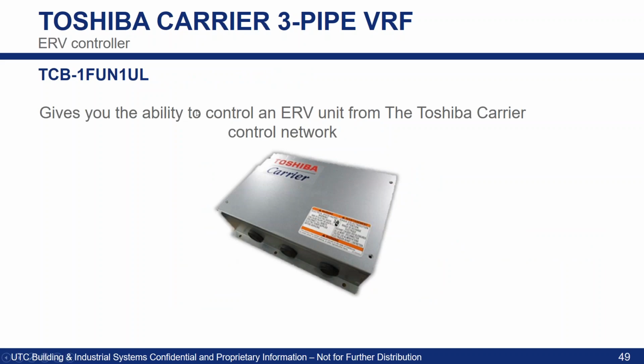So an ERV controller gives you the ability to control an ERV unit from a Toshiba-Carrier control network. So really, guys, this is the controller that we can integrate into our VRF control system that could turn on an ERV. It could also enable a DOAS unit. And this could all be run through our control system so it can be scheduled. So just a nice add-on there if you don't have a building automation system and you still want to be able to utilize our VRF controls, we do have something to where we could technically pull in a DOAS and control it.